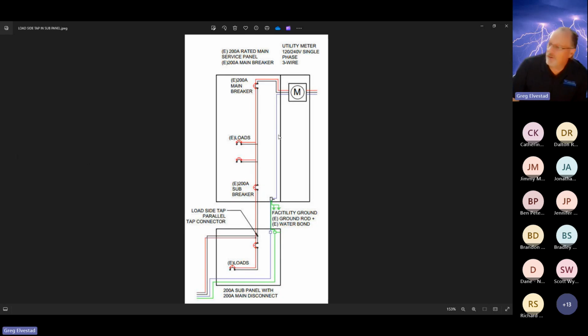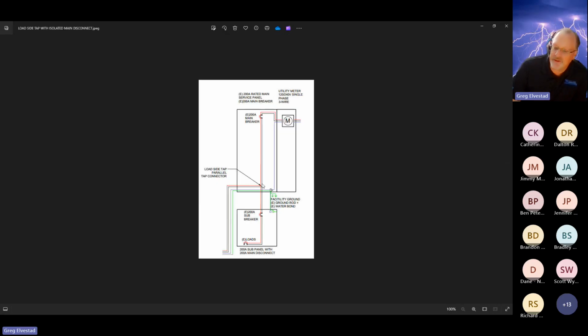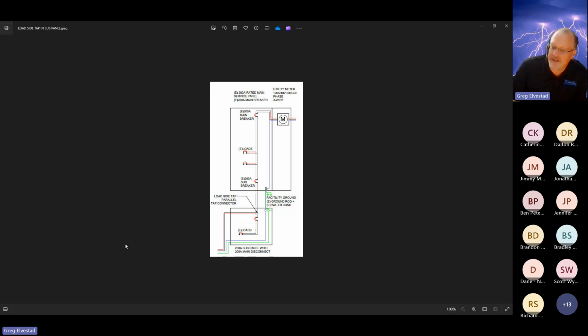Another option, I want to point out the difference between the two. Where are we making the tap? We're making the tap outside versus making the tap inside. Well, why do I want to do that? Well, sometimes you just can't get in here, and you've got to make a connection somewhere else. One of the other things I want to make sure you understand is the latest code, 2023, did have a stipulation on the distance between the main distribution panel and the remote distribution panel, that being 25 feet. So now you can still do the tapping like we said, but they want an overcurrent device ahead of it. I wasn't on the rulemaking panel, so I can't explain the why, but that's what it is.